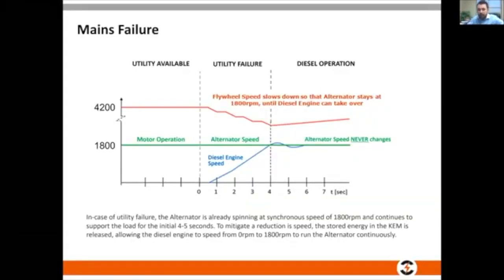Now, to show you a visual representation of speed, we have 3 distinct possibilities. We have the utility being available. Now, when the utility is available, you know the alternator is plugged in. And so you know the utility is spinning that alternator. It's in motor operation. Okay? It's going to spin and it's just going to sit there. The engine is off. The engine doesn't need to be on because the alternator is being spun via the utility. And my flywheel is fully charged. Stealing a terminology from batteries, it's fully charged. It's at 4200 RPM. At 0 point, so we have a problem, utilities failed, the input breaker's open, quality issues, whatever it is. My flywheel slows down so that the alternator doesn't.